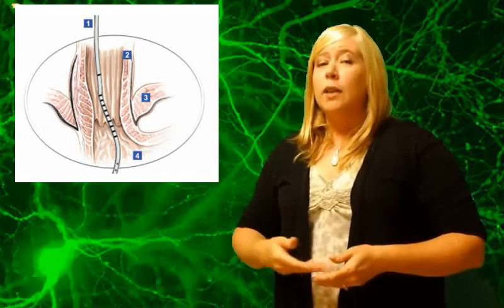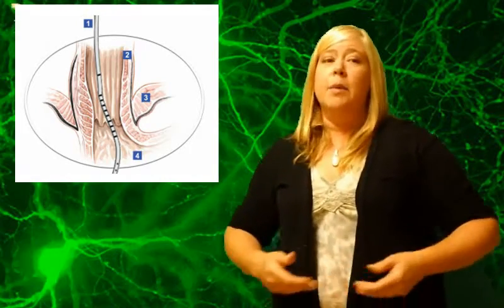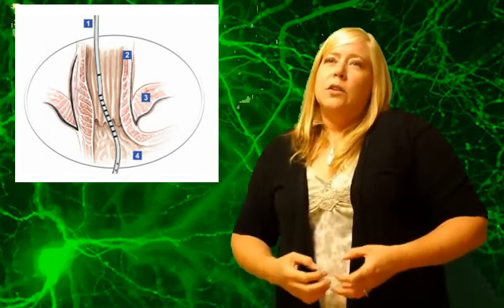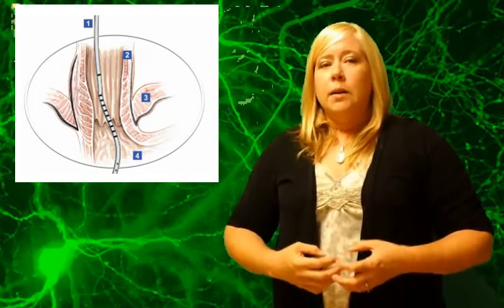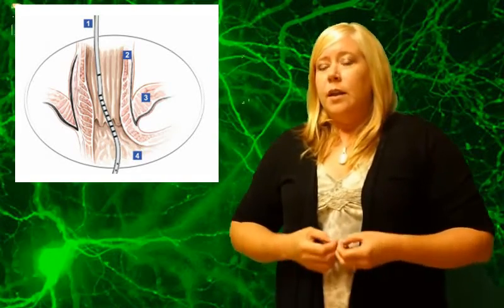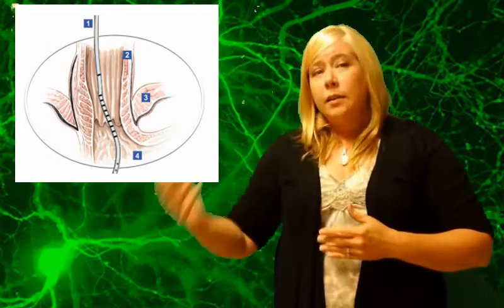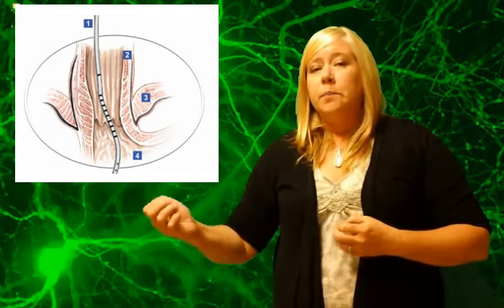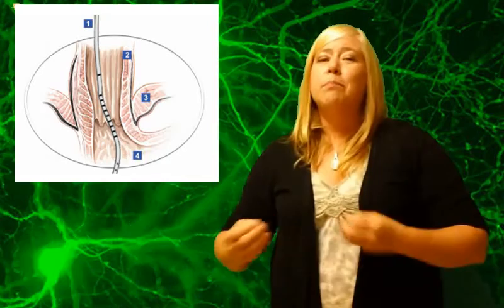So you can see we actually want those at the level of the diaphragm because we're picking up the signal sent from the diaphragm as the patient wants to breathe, and our neurons send signals down to the diaphragm telling it to go ahead, it's time to breathe. This EDI catheter picks those signals up and tells our ventilator that the patient wants to breathe. So we have better synchrony with our patient.